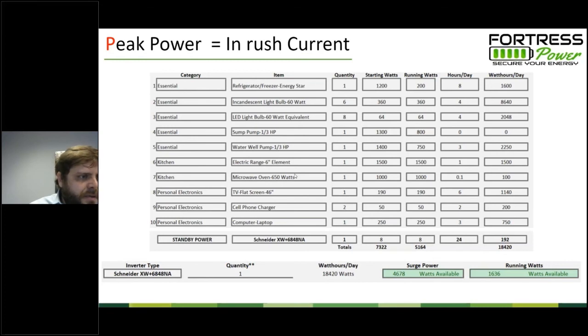So Pete, you have a question. Can the Fortress BMS be damaged when it disconnects? High voltage, overcurrent, temperature. Yeah, I can't get too much into the internals of the Fortress BMS, but what I can say is, it is slightly different depending on which battery you're in. Maybe the eFlex has a higher inrush current rating. It's also a little bit more of an expensive battery, whereas the eVault may handle inrush current differently, and that is more of a better approach when you're getting into 18.5 kilowatt hour batteries versus 5 kilowatt hour batteries.